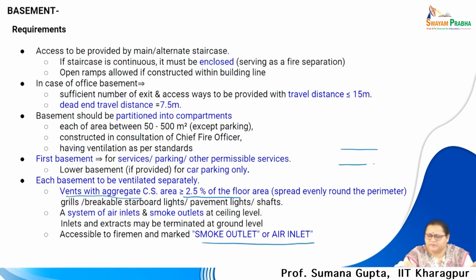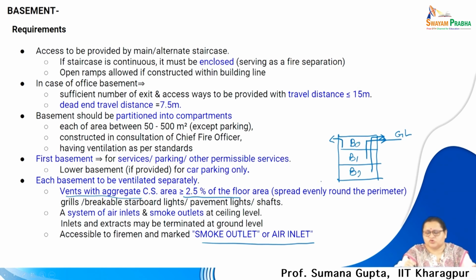If there are multiple basements and my ground level is somewhere here, each of these floors should throw out the exhaust, that is vent, from the ground level with proper suction systems. This is my ground level, this is basement 0, basement 1, basement 2. All these should have venting which should give out the foul air, or the smoke outlet, which will later become the smoke outlet in case of basements.